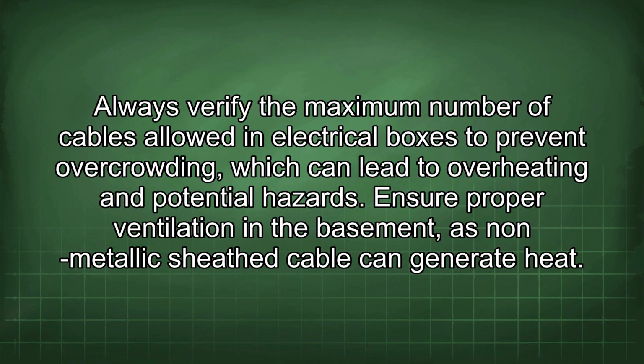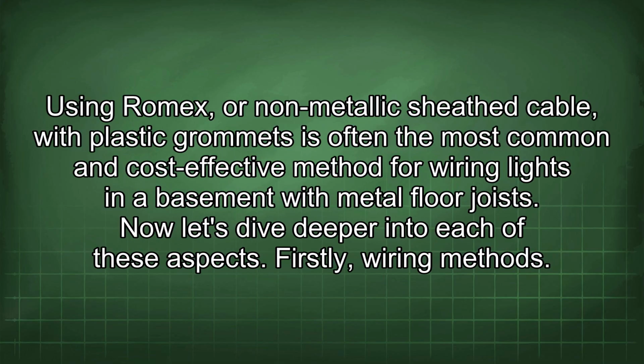Always verify the maximum number of cables allowed in electrical boxes to prevent overcrowding, which can lead to overheating and potential hazards. Ensure proper ventilation in the basement, as non-metallic sheathed cable can generate heat. Using Romex or non-metallic sheathed cable with plastic grommets is often the most common and cost-effective method for wiring lights in a basement with metal floor joists. Now let's dive deeper into each of these aspects.